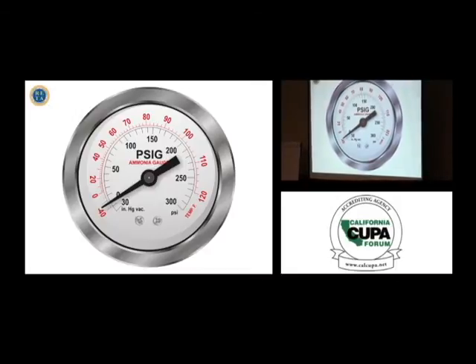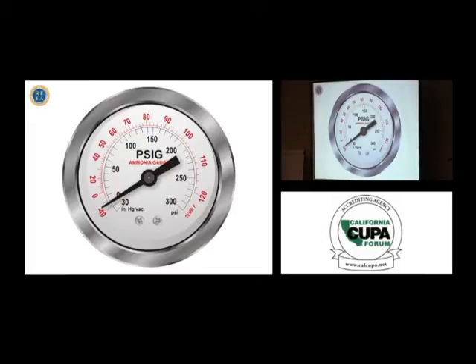Pressure gauges. You're going to be reading pressure gauges and recording them for me. And this pressure gauge has two scales. We have the pressure scale, that's the black, and then we have the red temperature scale. The temperature scale and the pressure scale correspond to the physical properties of ammonia when it's saturated. So as you're looking at here, this gauge is pointing to 0 psig, which corresponds to that minus 28 that you're all familiar with in the MSDS. That's when it's saturated. Sir?